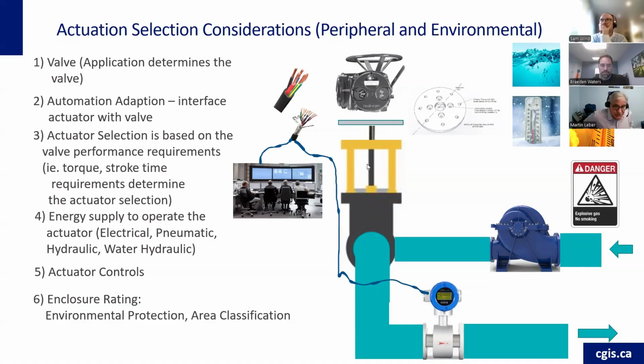And some of the applications that I've seen in the past, I've been amazed what environments can do to the coating of an actuator and get underneath the paint and cause it to literally peel off. So environmental protection and area classification is so critical. Making sure that the actuator enclosure rating is suitable for the area classification that it's being put into, and typically that's Class 1, Div 1, Groups C and D, but there's also a myriad of other environments that we need to ensure the actuator is suitable for use in.